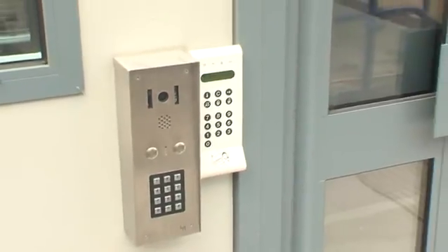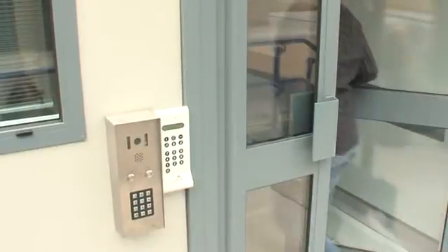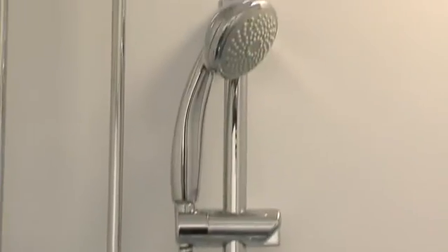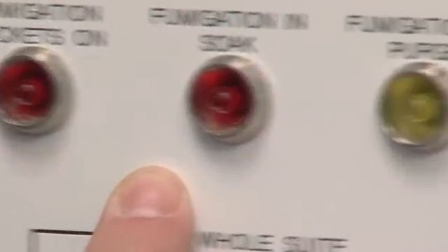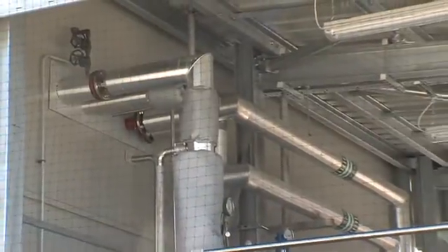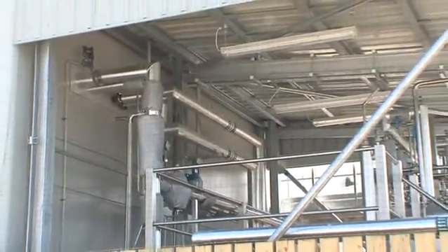Entry to and exit from the lab is strictly controlled. Access is key activated. Any person entering the lab must be authorised and security cleared. The entry and exit ante-chambers provide showers and other safety precautions designed to destroy all traces of any biohazard. The air and water systems going into and out of the lab are strictly controlled, and outgoing water and air undergo decontamination procedures to eliminate any possibility of an accidental release.